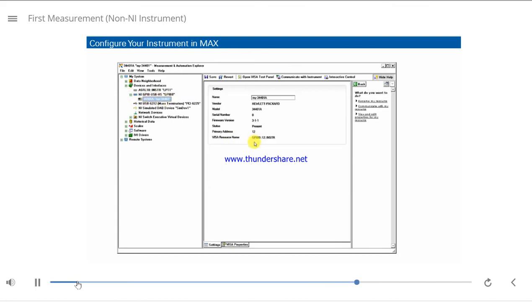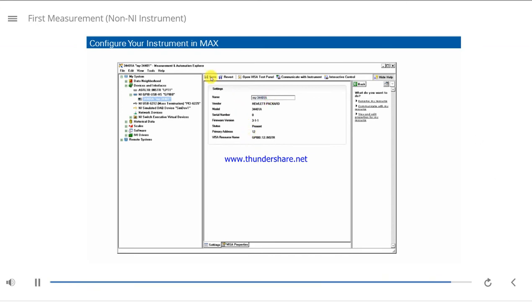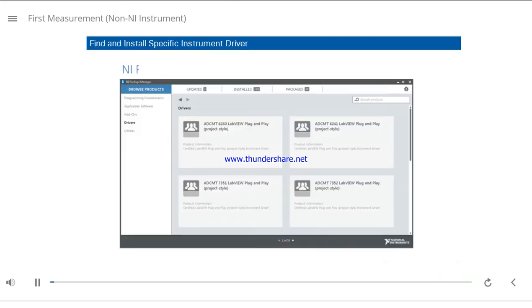On the Properties tab, notice that the default name for the instrument is based on a string containing the GPIB board number, primary address, and instrument. You can set a VISA alias for the instrument so you can identify the instrument more easily.